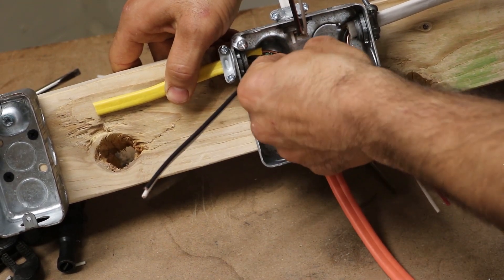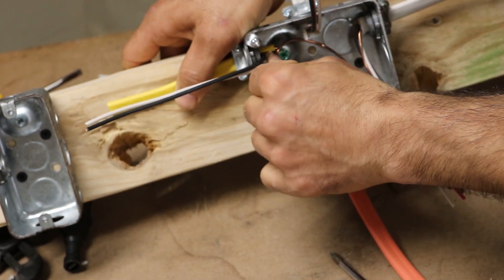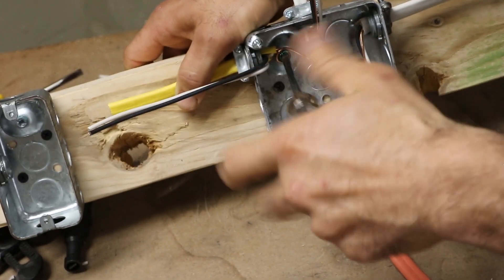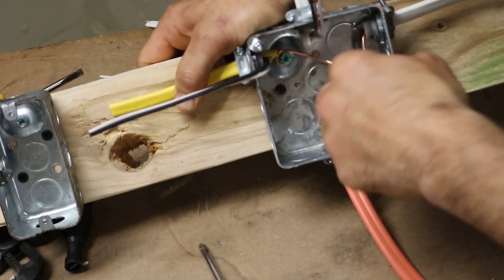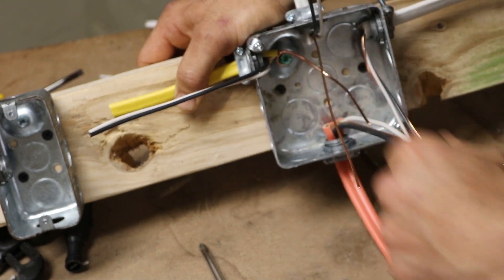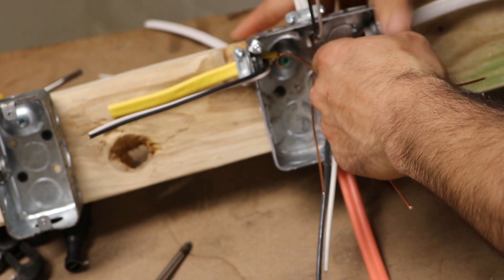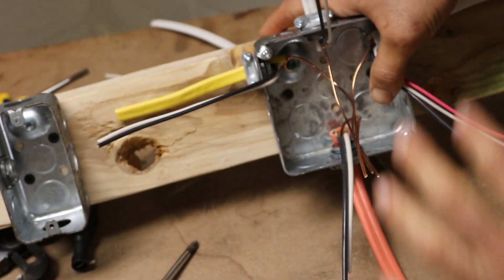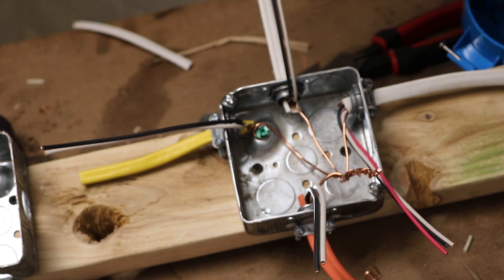Take a piece of one of your ground wires, doesn't matter which one, make sure you wrap it on there clockwise. You can either take some needle nose or something if you need to crimp it down. I feel like that's on there tight enough where it won't come off, and then you can tighten it down with a five sixteenths since it is a five sixteenths. Once you get it tight, you can take all of your ground wires. So all of your copper wires—if we're running pipe here, we'd have green wires—but we'll take all of those right here. And you will take a pair of lineman's and you'll tighten those up. So now that you got your grounds out of the way, you get your ground screw, your grounds, you can actually start wiring this schematic here.